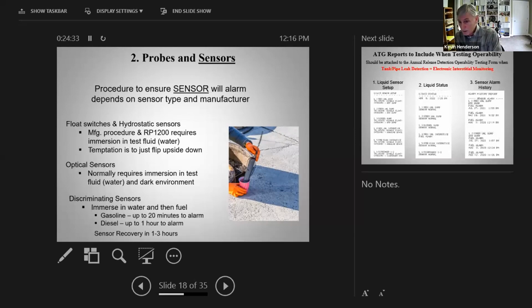But that really is all there is to it. I mean, that's it. An optical sensor, we do have some of these around. You'll see these typically, like an Omntec system uses a lot of optical sensors as an example. Optical sensors, again, you submerge it in a test fluid, but you just need to be aware that it has to be in a dark environment. So just putting it in clear water in a bucket out in the sunshine, you are not going to get an alarm on an optical sensor. It has to be covered up with a towel over it or have a very dark test fluid. It's got to be dark for an optical sensor to work.